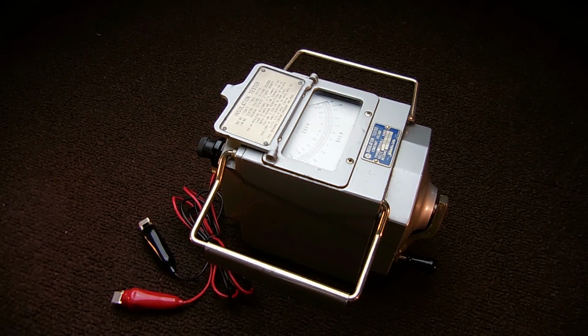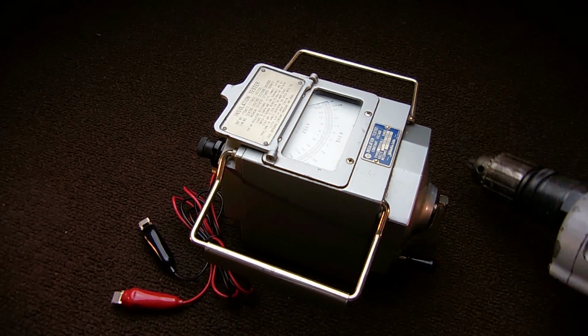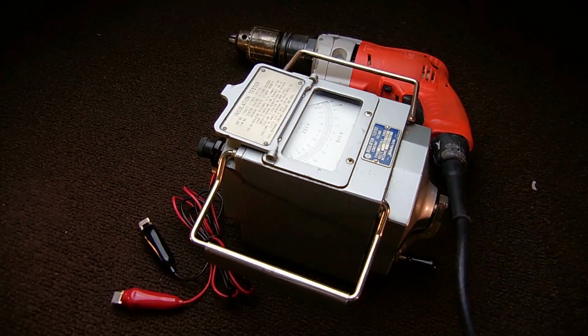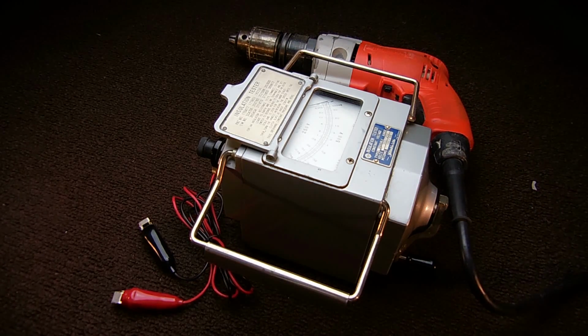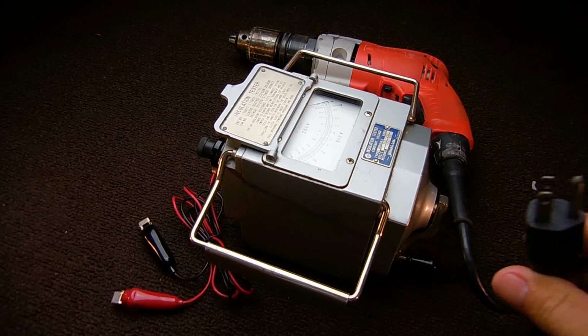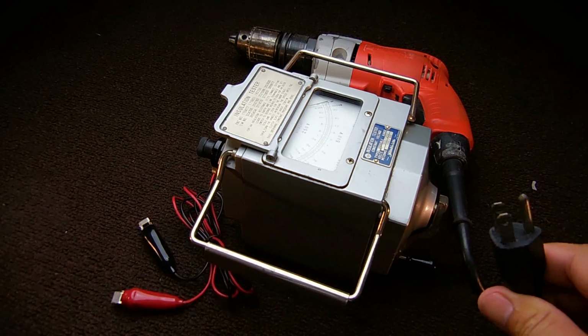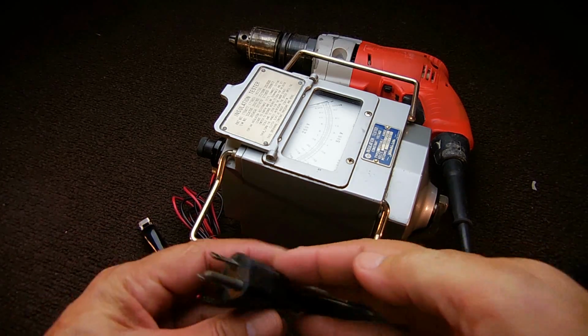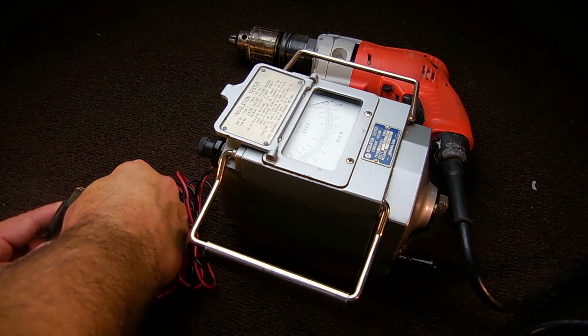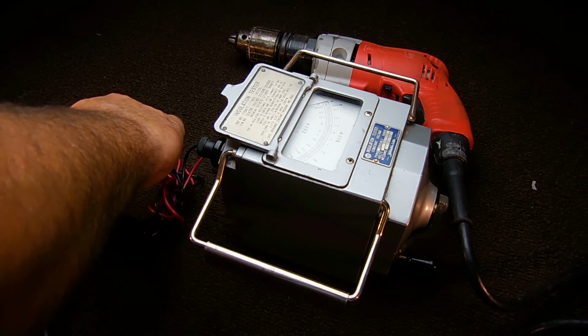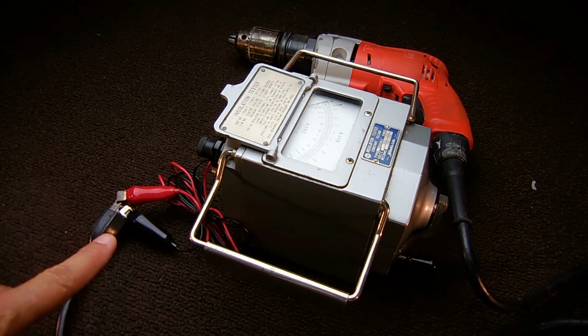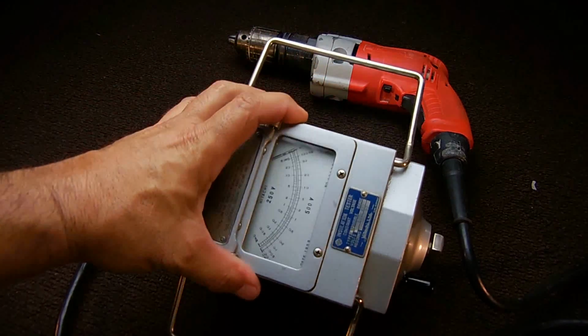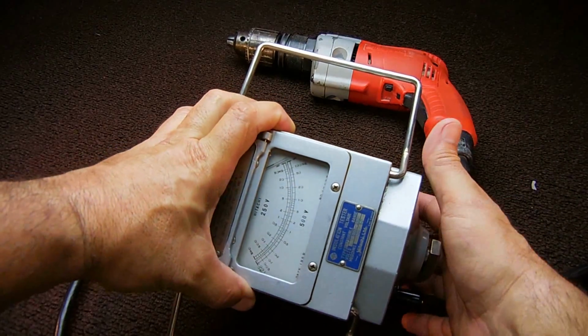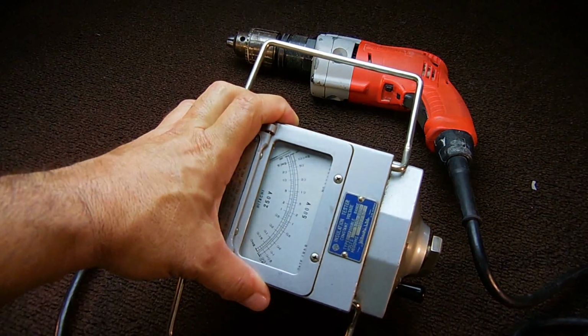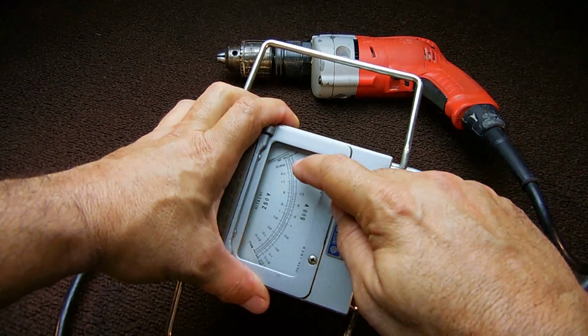You could test the condition of the windings within any motor. So we're going to be checking out this drill right here. So you push this over there. And what we're going to be doing, when you check these, you want to test between the ground and the neutral and the ground and the hot. So we take this over here, connect it to there, take that one to there. Make sure they're not touching. And make sure it's on a 250 because the drill is operated at 120. Give it a crank and it should stay fairly high.